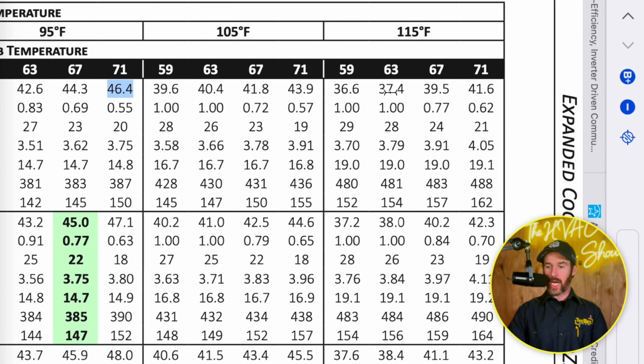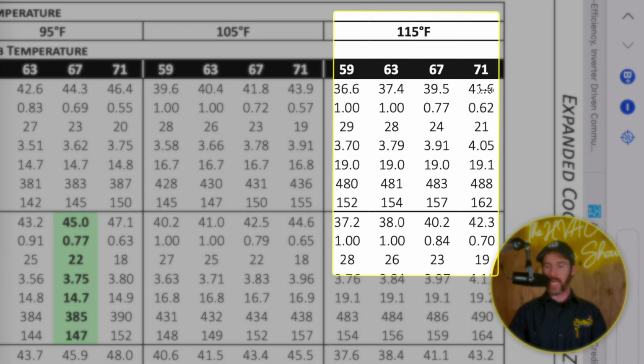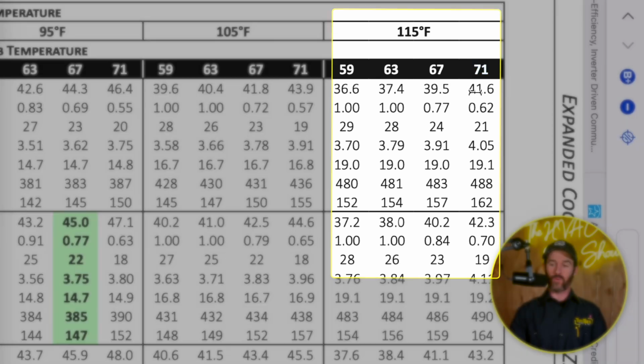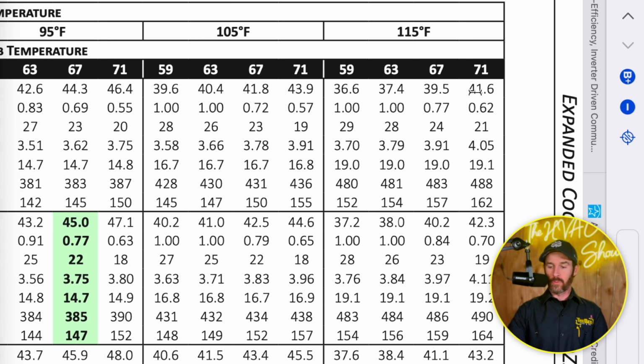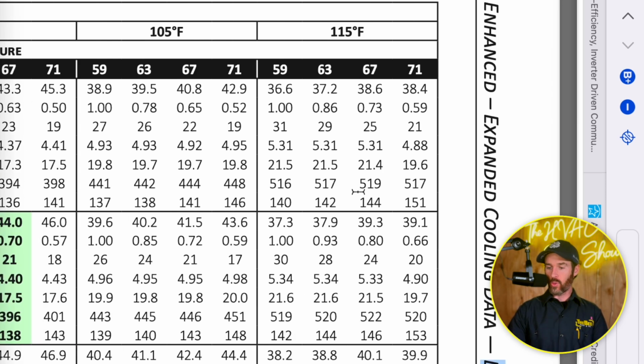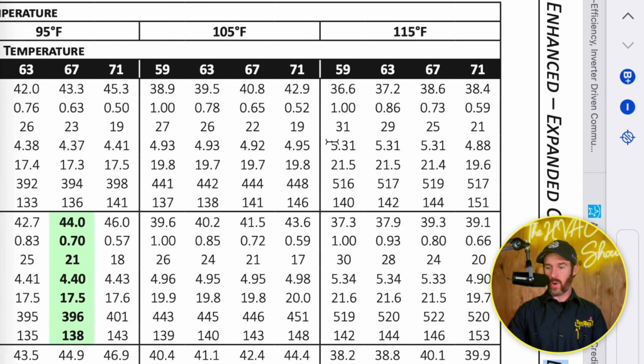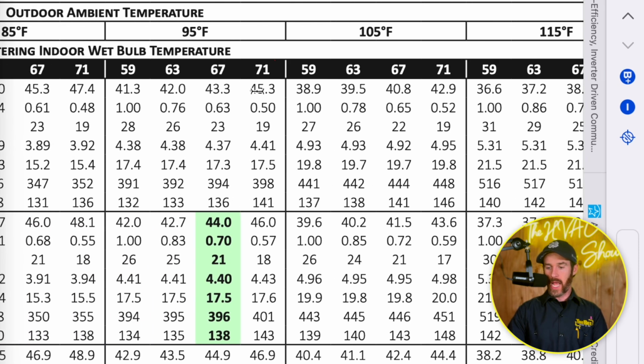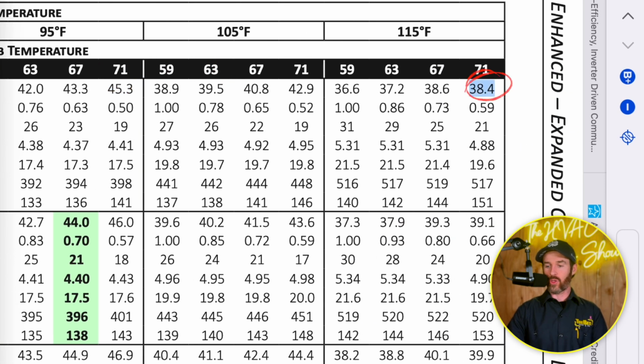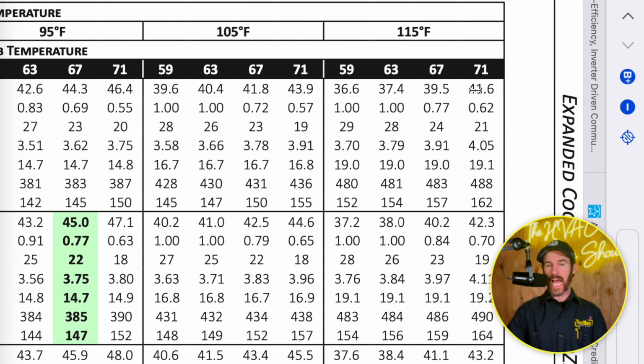And if you look at 115 degrees, this system still, this is the DZ9, this derates to where at a 71 degree wet bulb temp, it's putting out 42,000 or 41,600. We'll call it 42. So it's losing about 4,000 BTUs of capacity. However, if we go look at the Daikin Fit Enhanced, what we can see is that this system at 71 is putting out 45.3, and then it actually drops to 38.4. So it's not a huge difference.